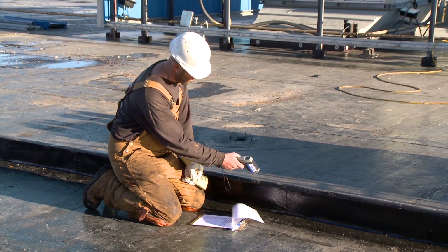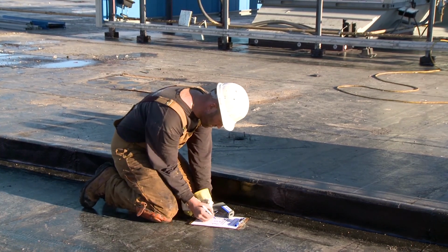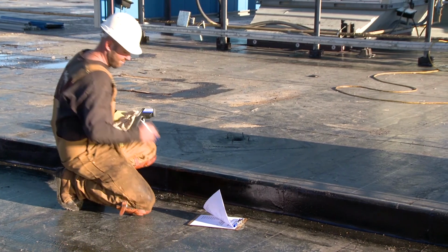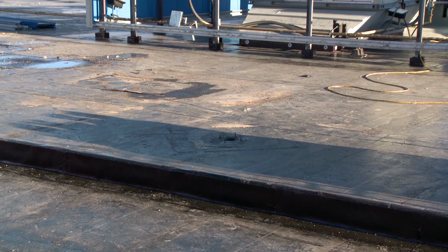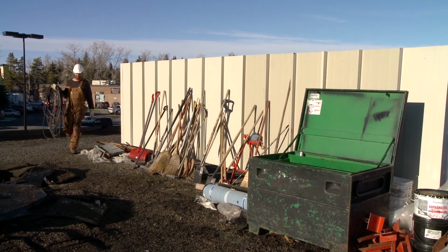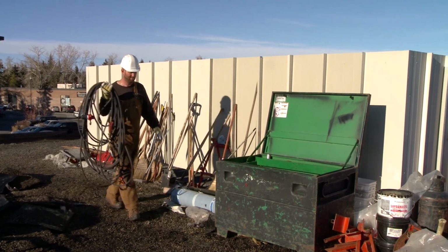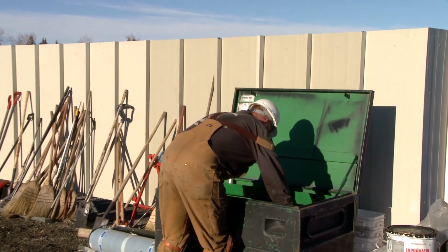A fire watch requires both visually and physically checking for rooftop hotspots and smoldering fires in concealed spaces after torching. Be alert to any unusual odors. Check all torching equipment, including propane cylinders, to ensure that they are shut off, disconnected, and properly stored. Make corrections as necessary.